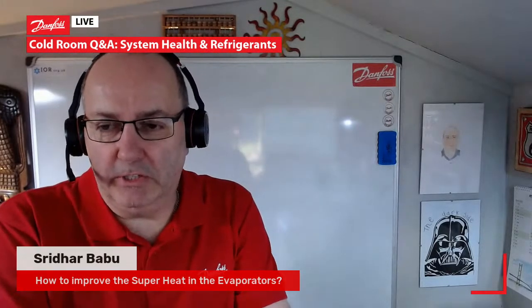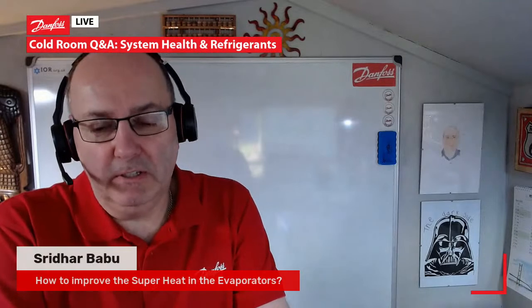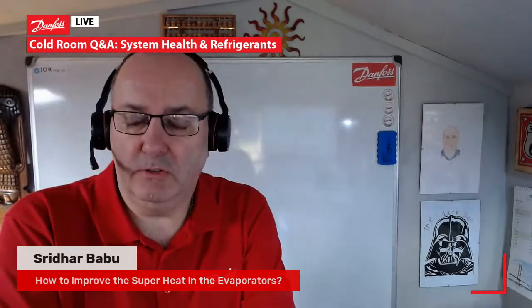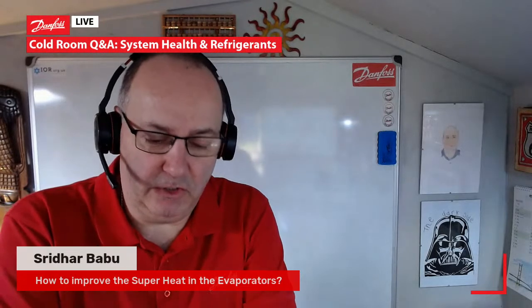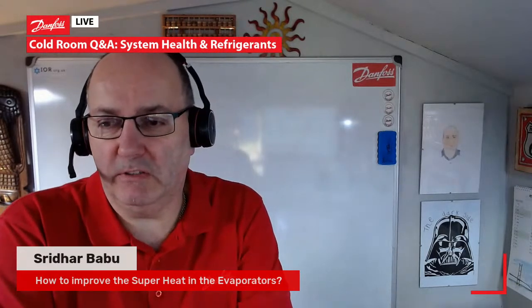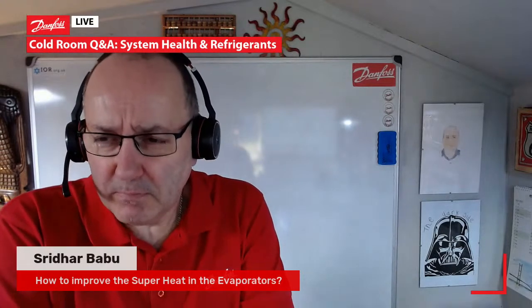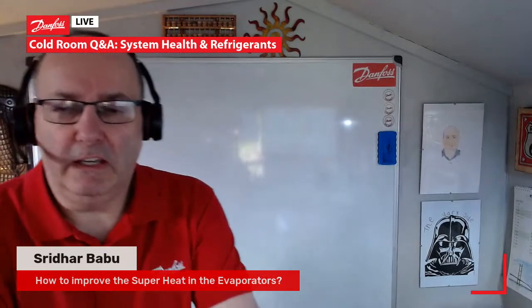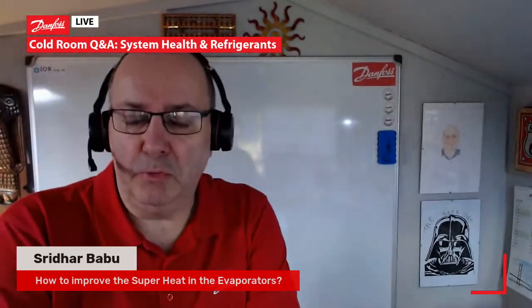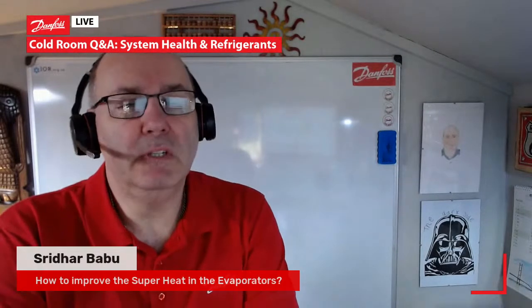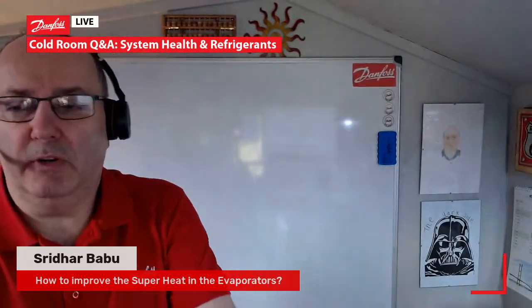If you want to control a very tight superheat, then an electronic expansion valve is, I would say, the way to go, because you can run a tighter superheat, so a smaller superheat, so you get more capacity out of that evaporator. Good airflow across the evaporator, things like that. If you want to have a very good superheat in an evaporator, then you run a flooded system, but that's more the realms of industrial refrigeration rather than commercial. So it comes down to the basics: good expansion valve, right capacity, right installation, good airflow across the coil. All those things will give you good capacity in your system.